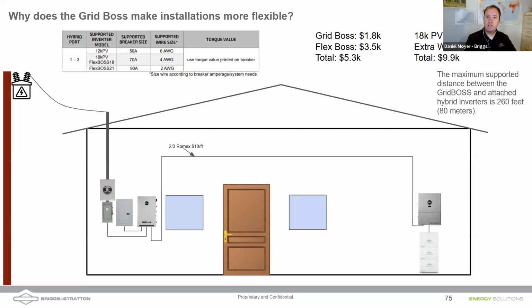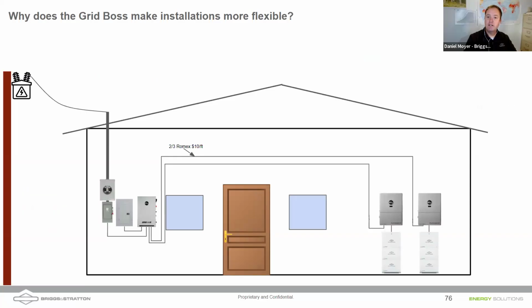This is where the grid boss comes into play. We can put that grid boss outside, right next to the service, right next to the load center. Instead of having to bring 200 amps over, 200 amps back, we only need one set of L1, L2, neutral, ground going over to a FlexBoss 21 or a FlexBoss 18, because we're only sending 90 amps at most between the two. We're really saving a lot of money, a lot of labor when it comes into doing something like this. And you don't need that disconnect if you're using the grid boss as your service rated entrance.